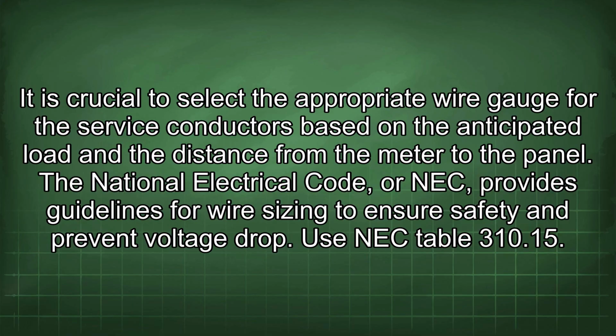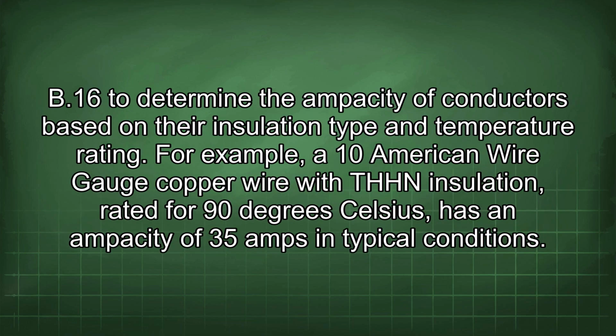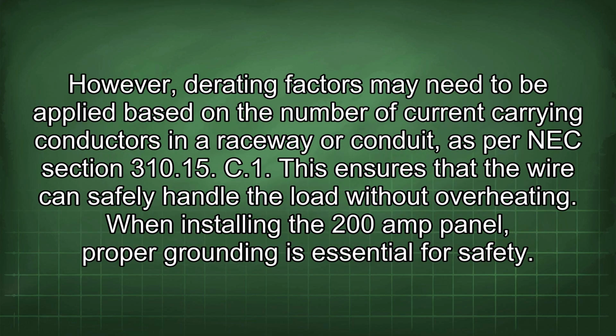The National Electrical Code, or NEC, provides guidelines for wire sizing to ensure safety and prevent voltage drop. Use NEC Table 310.15(B)(16) to determine the ampacity of conductors based on their insulation type and temperature rating. For example, a 10 American wire gauge copper wire with THHN insulation rated for 90 degrees Celsius has an ampacity of 35 amps in typical conditions. However, derating factors may need to be applied based on the number of current carrying conductors in a raceway or conduit, as per NEC section 310.15(C)(1). This ensures that the wire can safely handle the load without overheating.